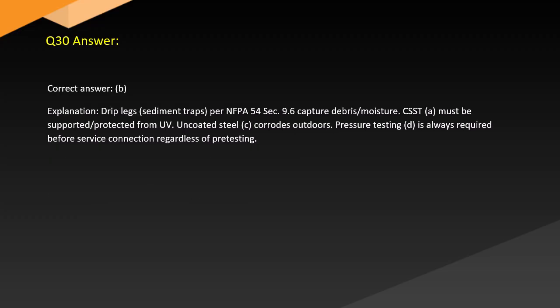Answer. Correct answer: B. Explanation: Drip legs, or sediment traps, per NFPA 54 section 9.6, capture moisture. CSST must be supported and protected from UV. Uncoated steel, C, corrodes outdoors. Pressure testing, D, is always required before service connection regardless of factory testing.